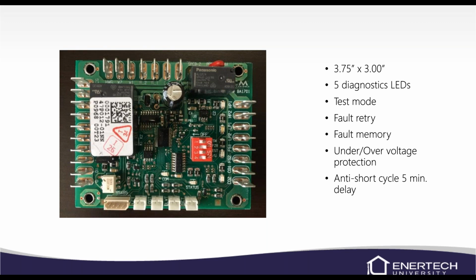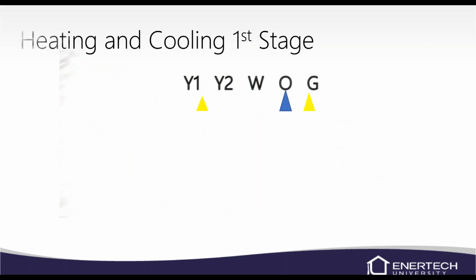It has fault memory to a certain extent. If we remove power, high voltage power to the unit, then we erase the codes off the board. There's no battery on this board to store the codes. So a power interruption would delete the code in there. We do have under over voltage protection and a 5-minute anti-short cycle timer in between on-off cycles. So, a little bit of the sequence of operation on the board itself.